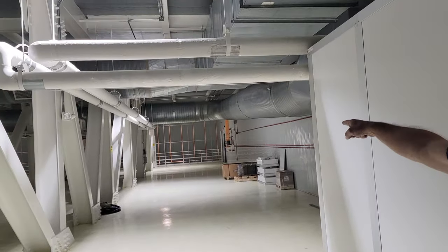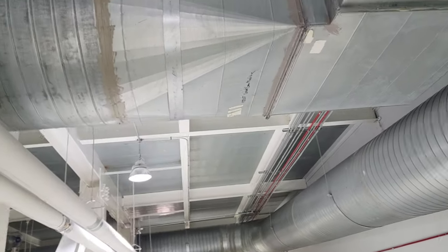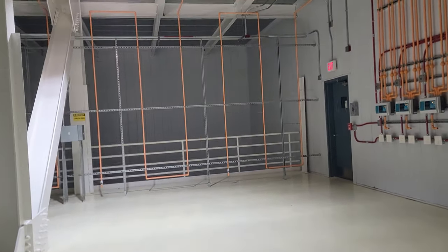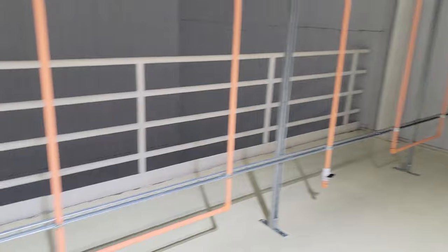Is the air coming in through this here? Air coming in from the opposite side. You can see the orange coatings, the vestibules — they're sampling the air as it's coming up. What are these tubes above our heads? Fresh airs — that's just coming into the building. Your return is coming down this chase. This is coming from the clean room. What's this PVC stuff? That's all sampling tubes — they're sampling airs, going through and reporting back. These are the sensors. That's a differential that drags it across, probably an optical sensor of some sort. And in case of fire it can shut it down.